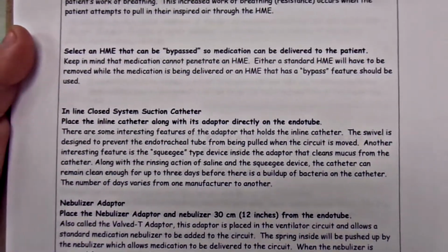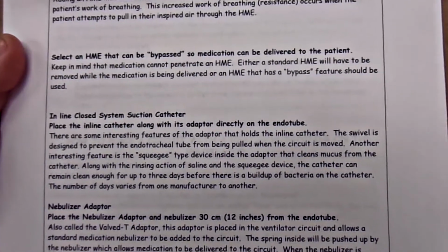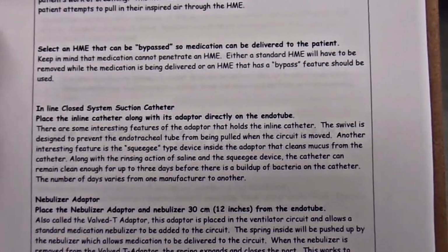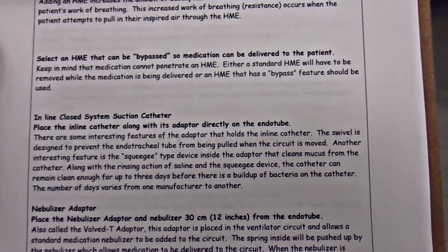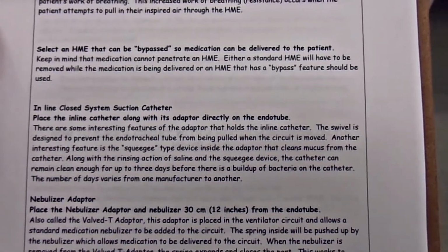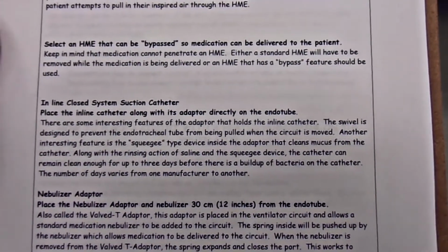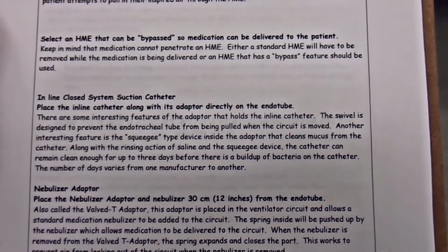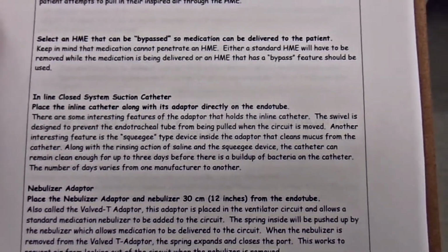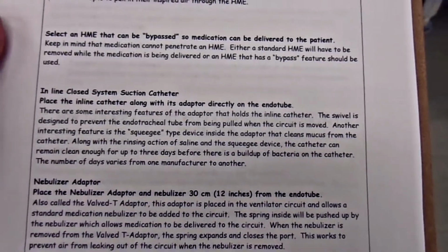Select an HME that can be bypassed so medication can be delivered to the patient. Keep in mind that medication cannot penetrate an HME. Either a standard HME will have to be removed while the medication is being delivered, or an HME that has a bypass feature should be used. Okay, we already talked about that.